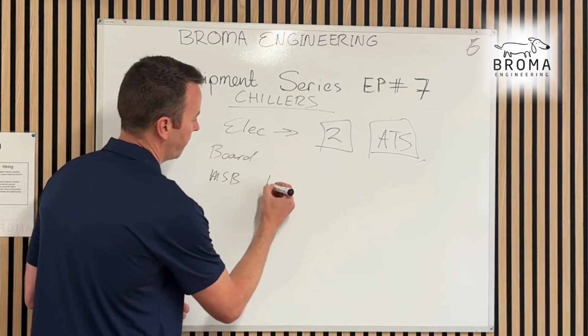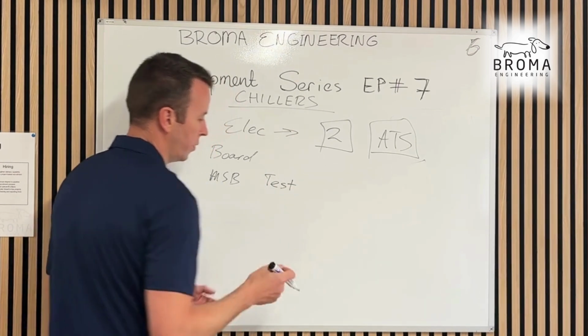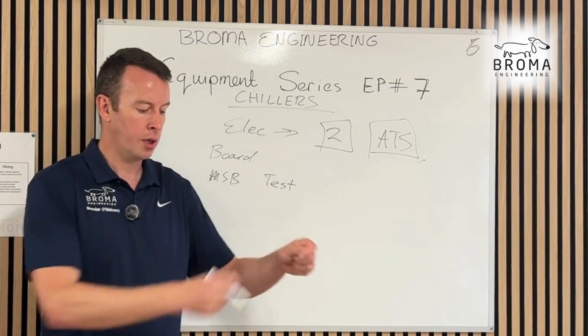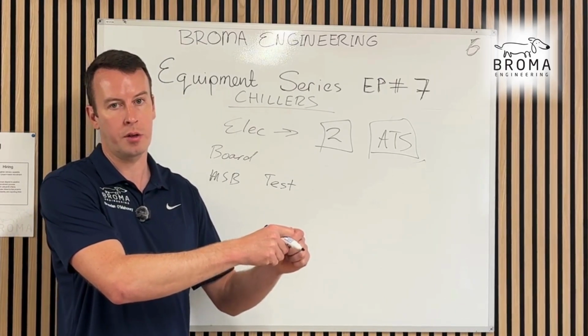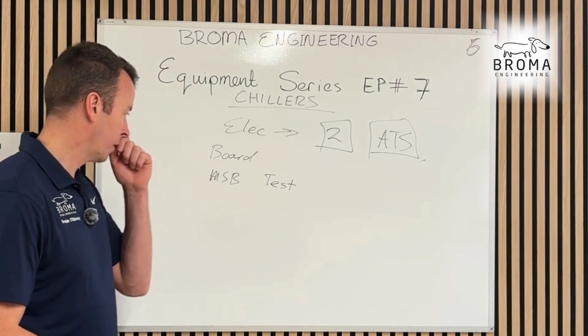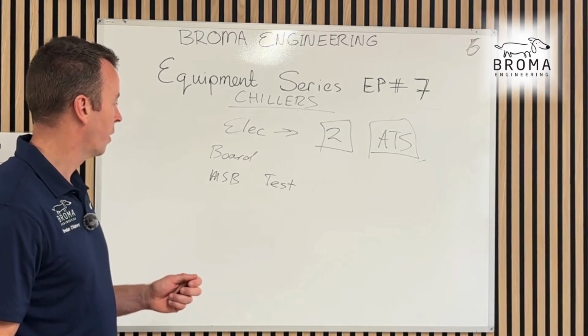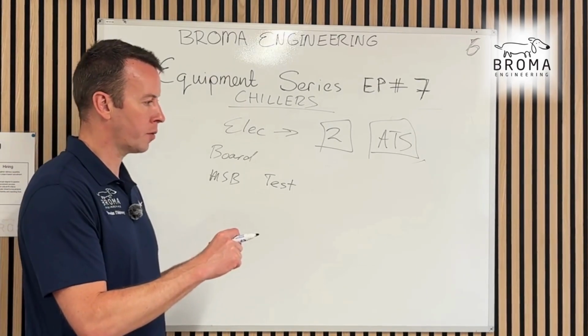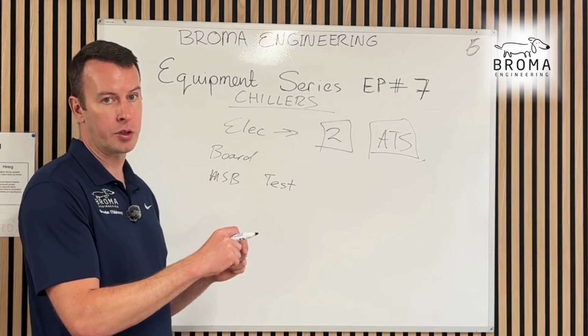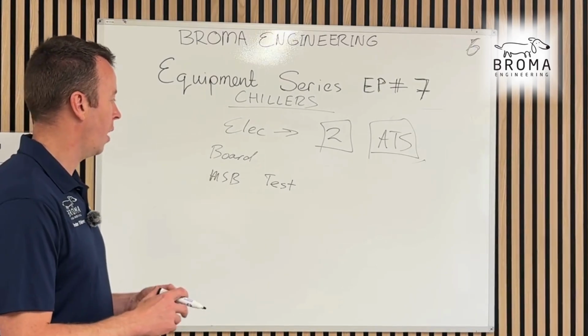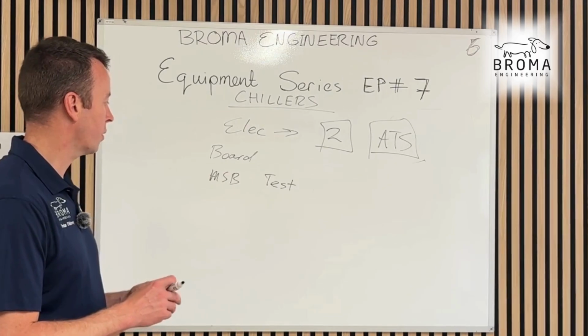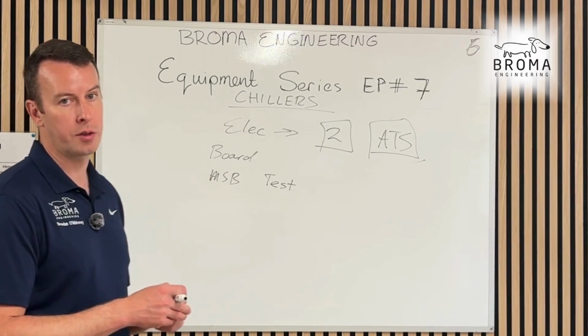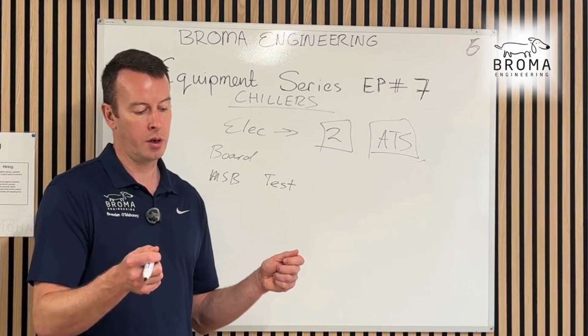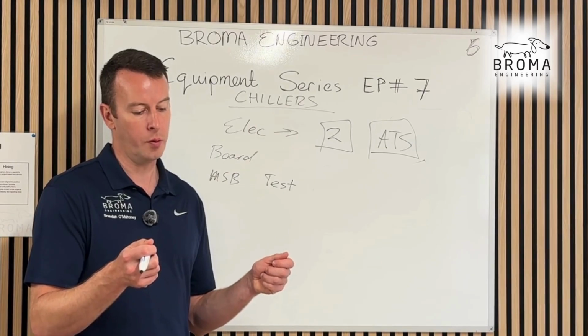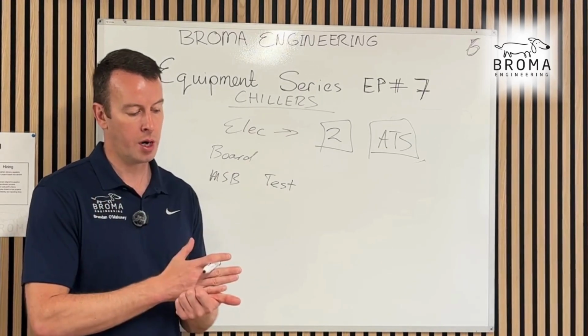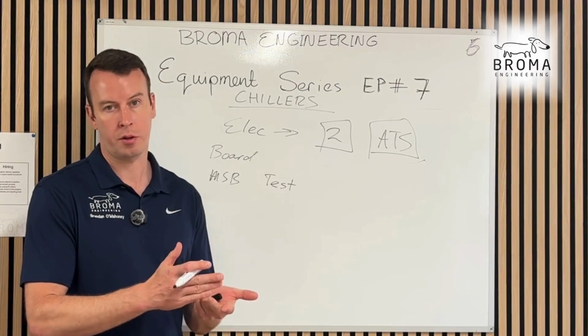The cables will have to be tested, and then they'll have to be torqued. So once they've tested the cable - and we'll do another video on that - they'll have to torque each end and put a torque mark on the bolt that's holding the cable to the supply in the chiller. They'll have to be cable labeled. Sometimes that can hold up a tag, you don't want that, make sure that's done. So the electrical team keep asking. We'll do another video specifically on cable testing, because it really does hold up jobs. Until that cable is tested and you've got the test sheet up against the asset, and we can prove it's tested, marked, the right color, torqued - they might even need pictures.